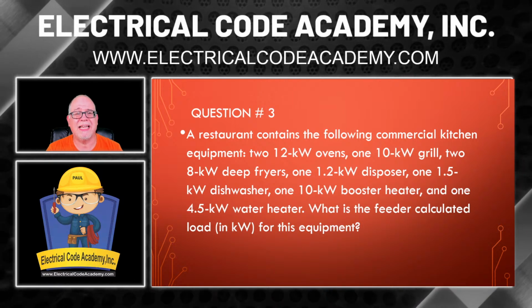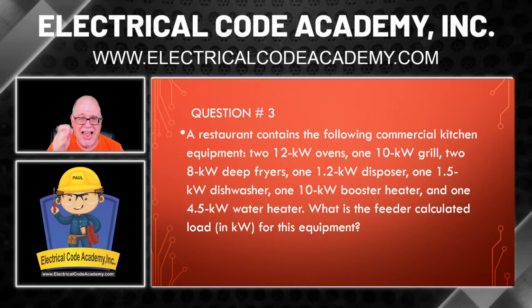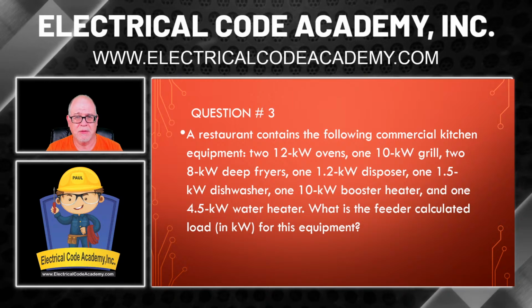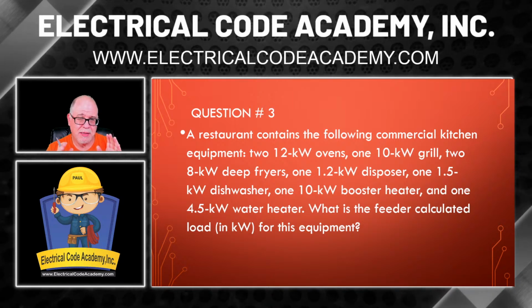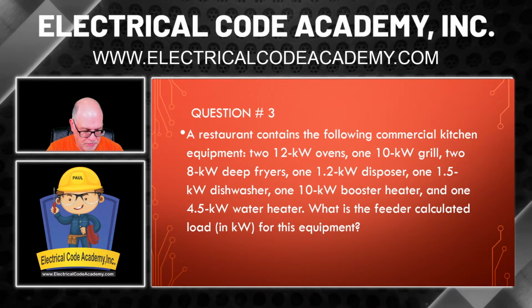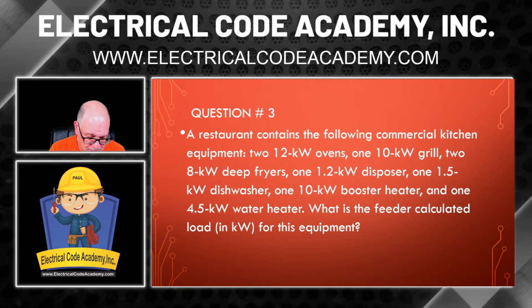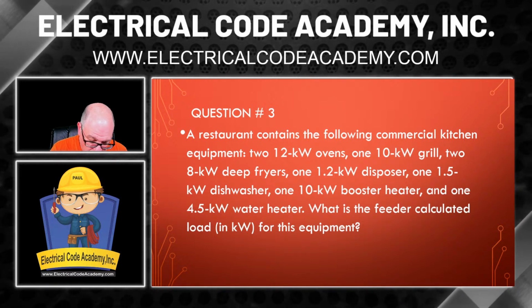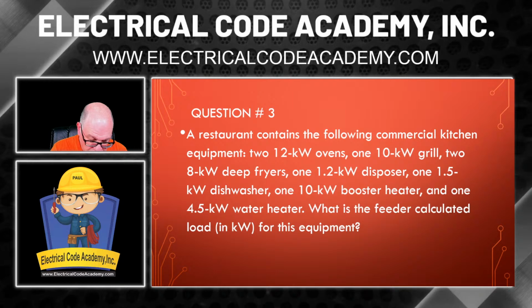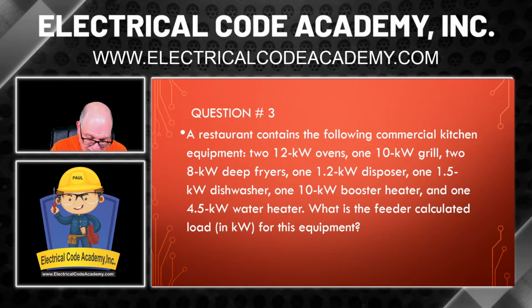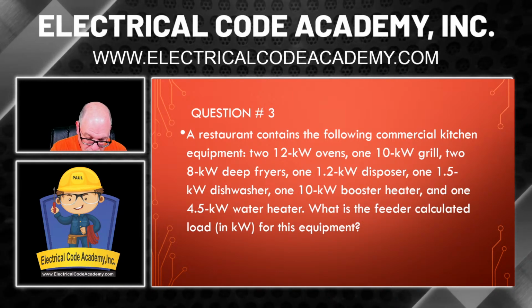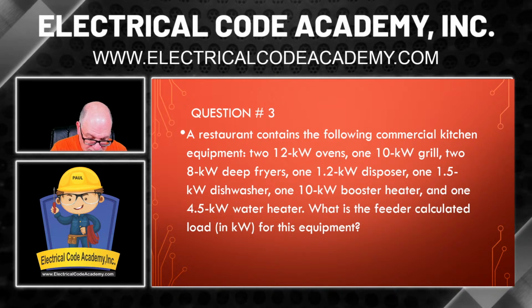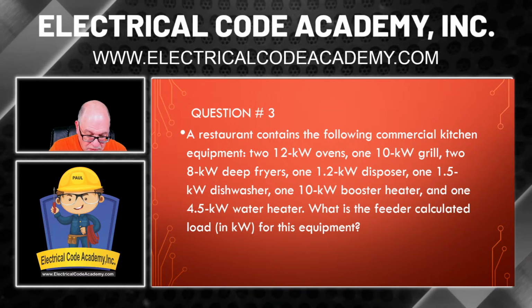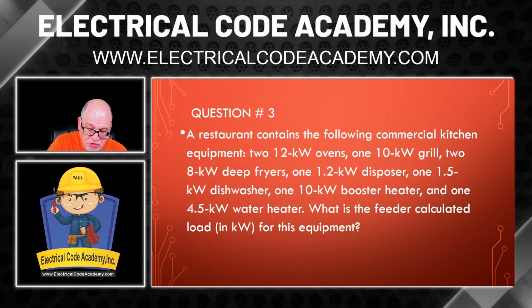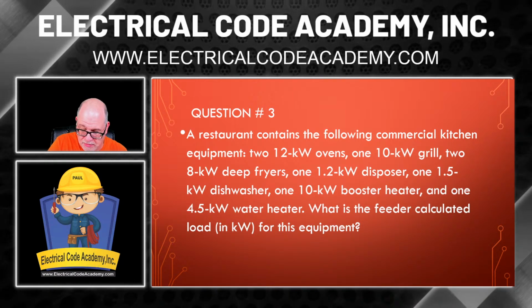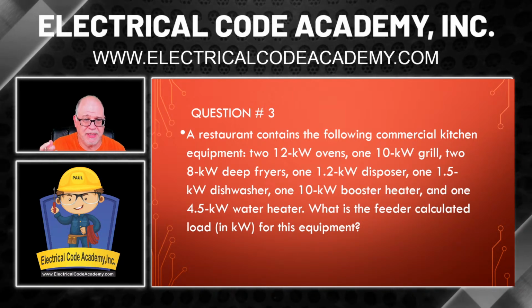I want to go on and get my total connected load. So I want to add everything up here, okay? Remember, you can pause this at any time, but I'm going to do that first before I even start looking at the code. So I'm going to add up 12 plus 12 plus 10 plus 8 plus 8 plus 1.2 plus 1.5 plus 10 plus 4.5. That gave me 67.2 kW, okay? So at least I know what they're all added up to be, right?